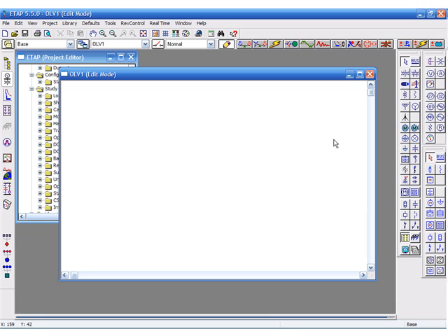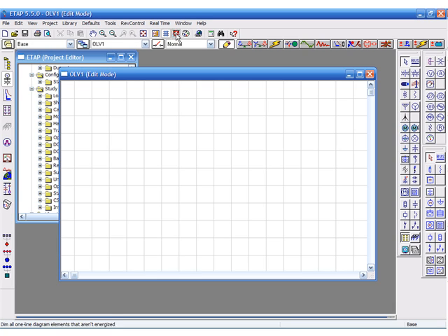You can turn the grid on and use it as a reference for spacing between elements, like this. Right next to it, you'll see our continuity check. Let's make that active. That way elements other than the power grid or utility are shown in gray when they're de-energized. Let's drop a couple elements down on the one line. As you can see, the grayed out ones are de-energized because of our continuity check.